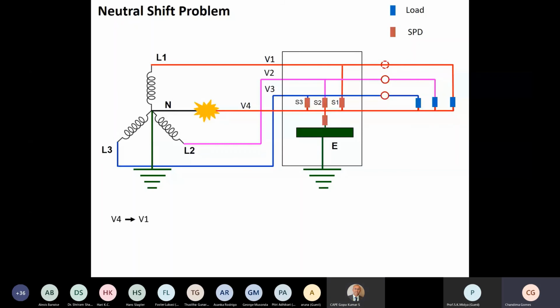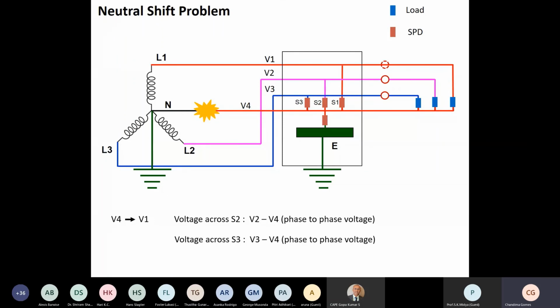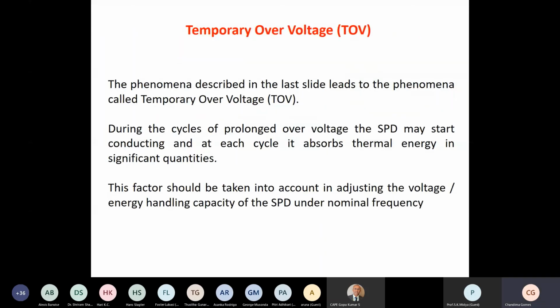Now you will see that the voltage across SPD S2 and S3 becomes line to line voltage, so that your SPDs are now exposed to line to line voltage rather than line to neutral voltage. So that will most probably damage your SPDs, unless, this is what we call the temporary overvoltage, unless your SPD has a TOV rating which is able to withstand for quite a long time this type of line to line voltage.